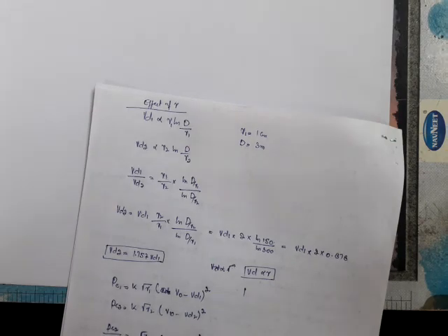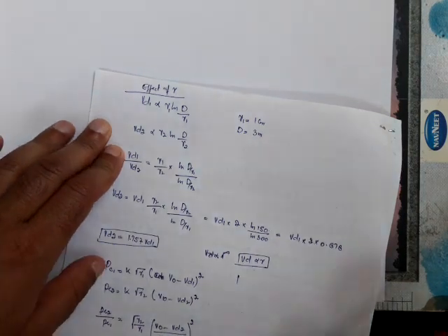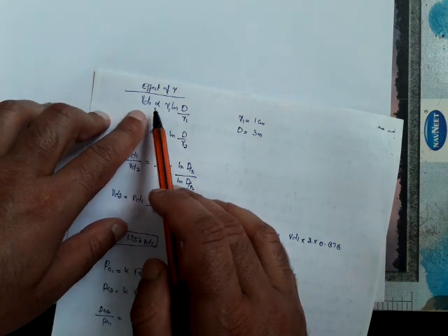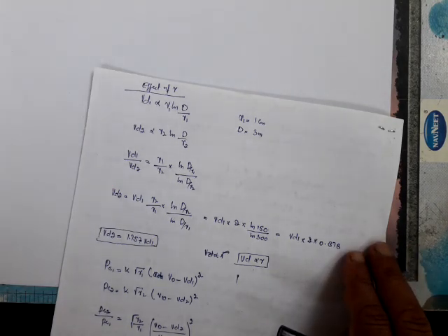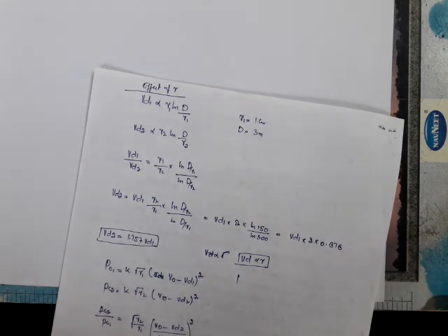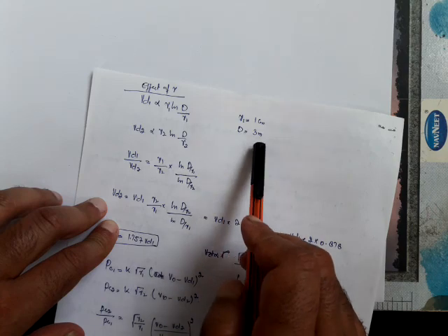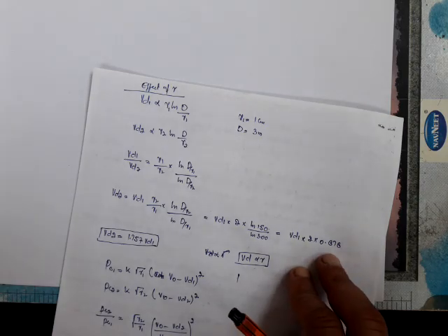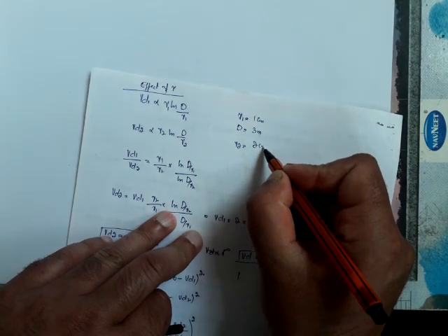So we come now to the radius of the conductor, which is slightly complicated, but we'll do this. Let us say I compare Vd1 with the two systems. For system 1, Vd1 is proportional to R1 ln of d by R1, and in both the cases we keep the distance same, but we only change the radius of the conductors. Vd2 is equal to R2 ln of d by R2. Let us say R1 is equal to 1 centimeter, d is equal to 3 meters, and in the second case we will increase R2 to double of R1, that is R2 is equal to 2 centimeters.